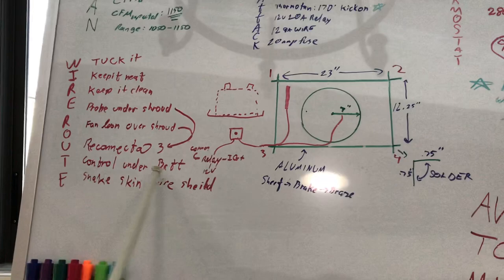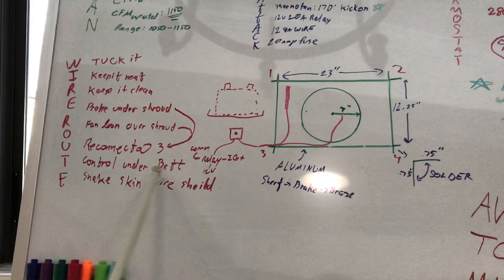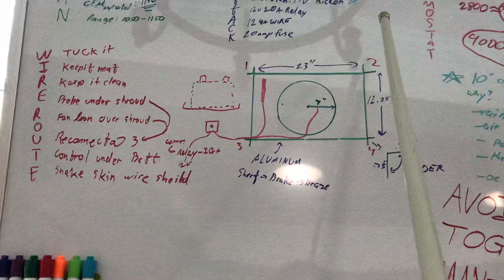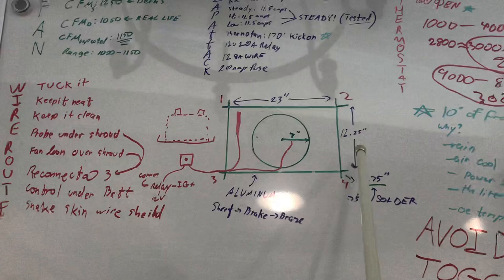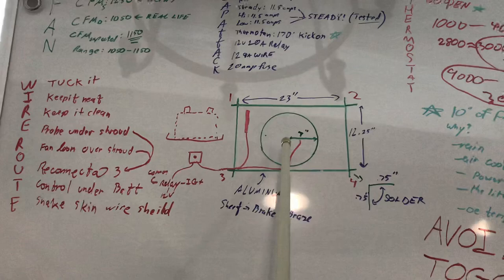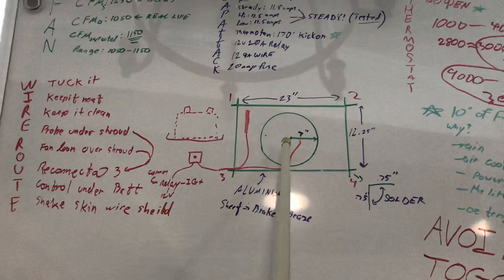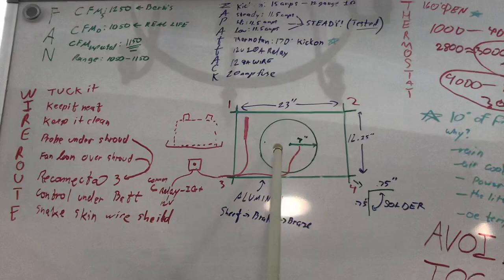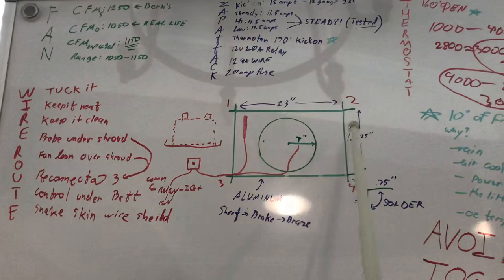Here's the drawing of the shroud. I didn't buy a shroud, I actually made one, so I've already done all this, I just haven't installed it yet. If you have a keen eye from the beginning of the video you were looking at this, you may see something wrong. 12.25 inches is our overall height, 23 is the length, but you can't have a fan of radius seven. That means the diameter is 14 and it wouldn't fit here. I did this on purpose that way you know, okay, if I have my measurements, don't go over it because it's not going to work right.